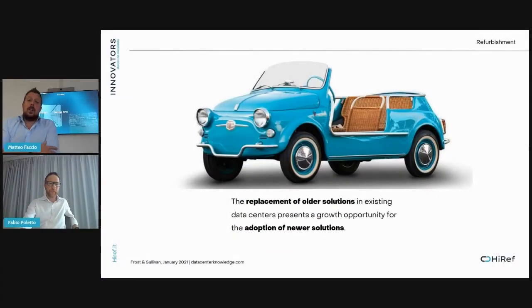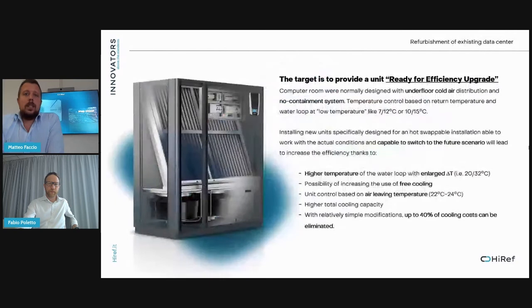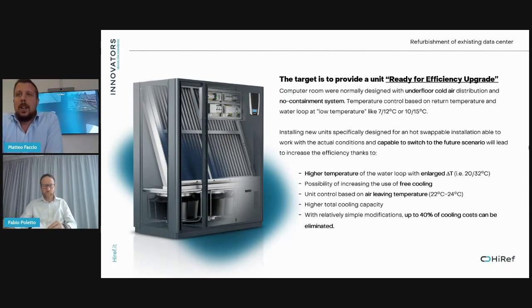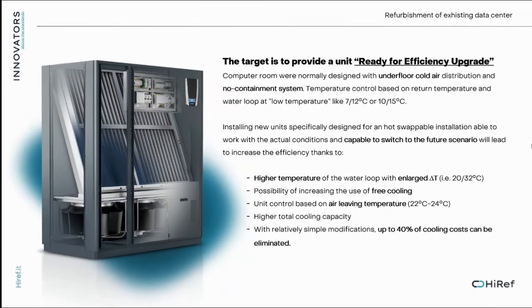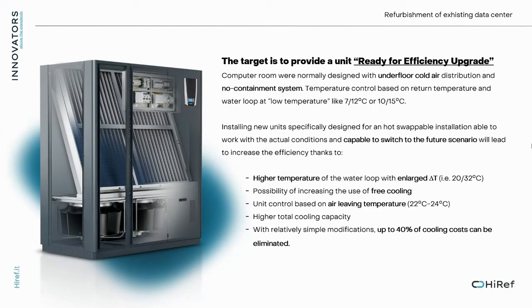That's true, Fabio. There are a lot of data centers still running and not yet arrived at the end of their life, let me say. So we need to give this customer a solution. We need to give this customer a product that is ready for an efficiency upgrade. This is the example of the unit that you can see here in the slide. This is a unit that is completely flexible. It's able to work with the old low temperatures like 7/12 or 10/15, and it is able to be installed in a hot swappable condition. It means that you can replace older units with this new unit while the data center is running. That is another key point to guarantee continuity.